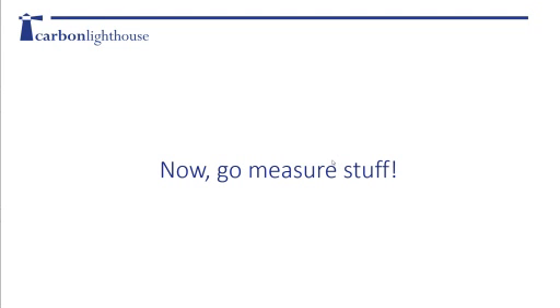How did you do that last graph of temperature versus outdoor air temperature? Any time you go to a building, you should always launch an outdoor air temperature sensor. What you're interested in is how a building is used over what sort of outdoor air temperature regimes. Simply measuring discharge air temperature without some correlated reference isn't the most helpful information. To get that, we just launched a second logger on the roof. If you don't have another logger, you can download data from NREL or NOAA weather data - just make sure it's the quality-controlled version.